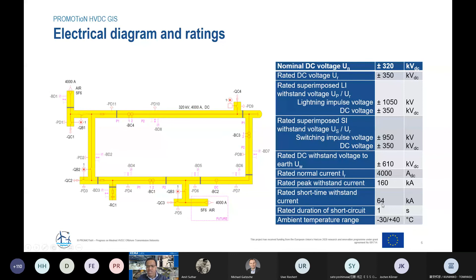The test program, of course, as I mentioned, is a prototype installation as it will be in service. That means there are lots of procedures. The first one is a pre-test. A pre-test is, of course, to make sure the installation is correct, everything is correctly installed. Then check if it is ready for running. That means the thermal cycle by applying current through the bus bar, and also applying lightning and switching impulses, and partial discharge measurement before the start to make sure everything is okay.